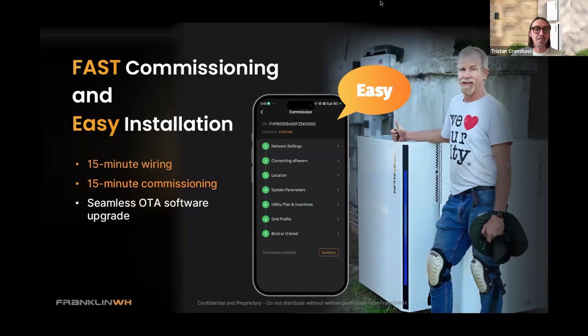The aPower S also has very fast commissioning, 15 minutes or less. So if anyone has installed Franklin before, they know our commissioning is very quick and easy. There are only a couple extra steps for the aPower S—you just have to notify that you have PV connected to it and what type of interrupter, MCI, or rapid shutdown you're utilizing. Those are basically the only extra steps, so very, very fast. And then we can seamlessly transfer any software or firmware updates over the air easily.